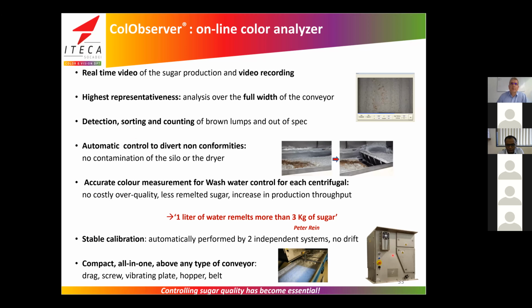Okay, so the window of the system is located at this level, not at the bottom. So it means that in this area, we have a very calm location without any dust and so on. And usually we ask the customer to clean the window on white sugar at each campaign or every 3 months. But it's not very important to clean it because usually it's very clean. But in the case of dust, because we are working on dry sugar, in this case, we ask the customer to clean the window every week.